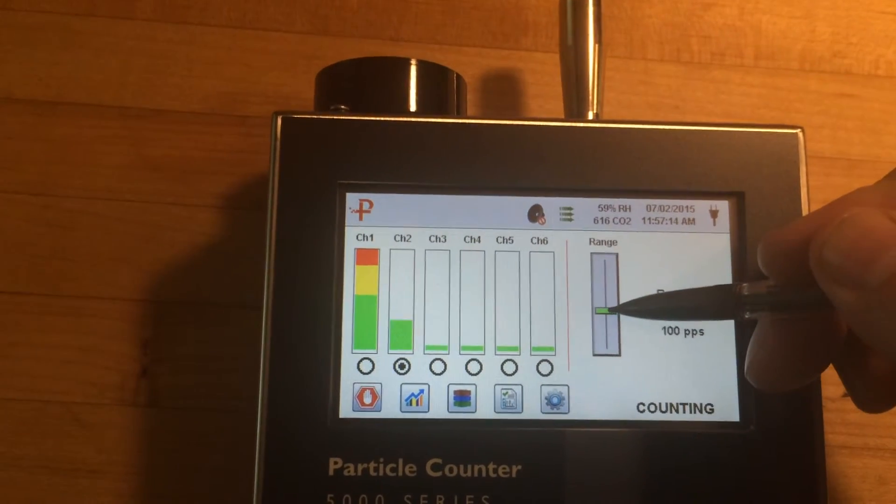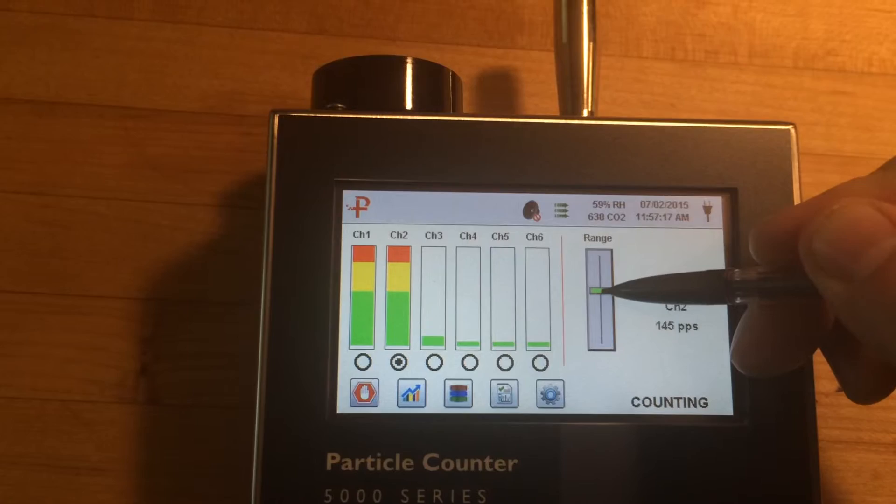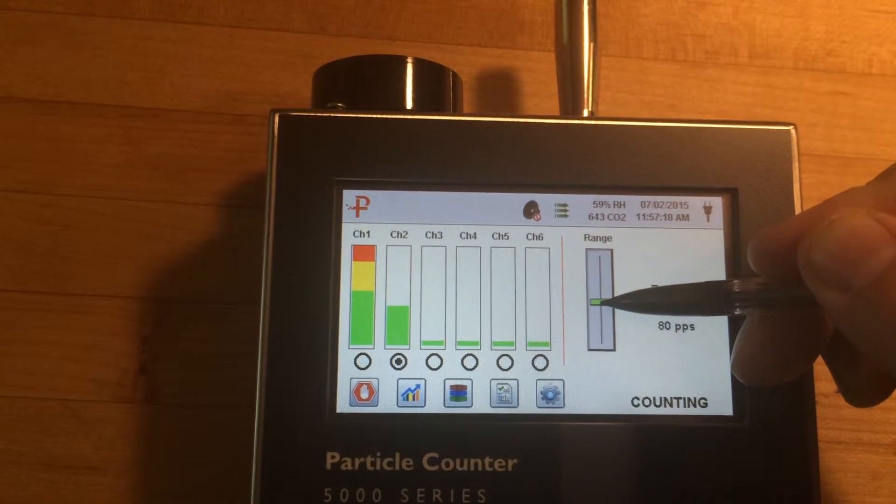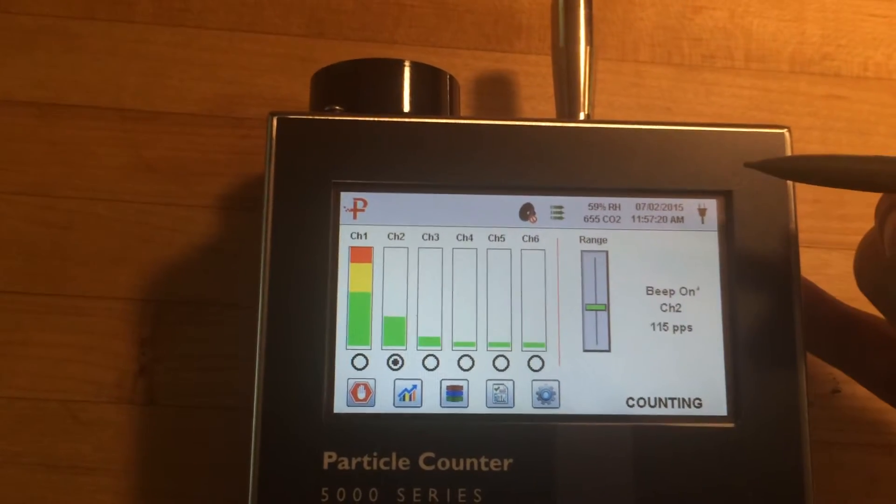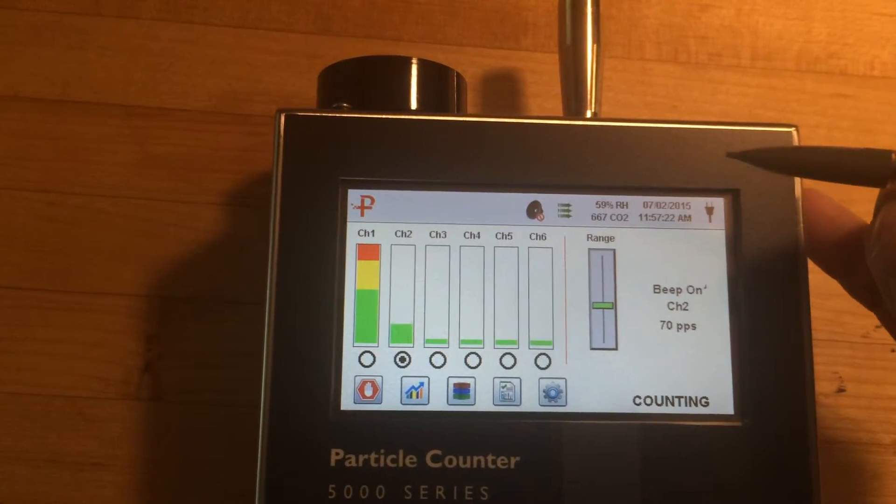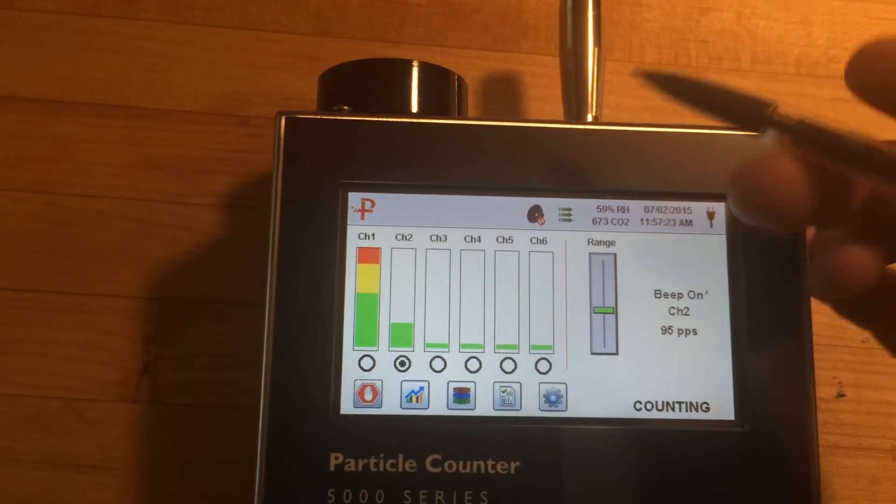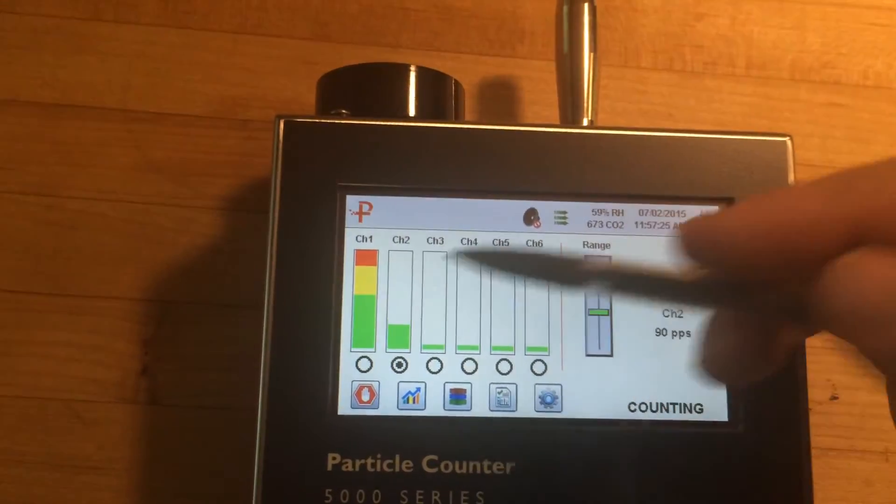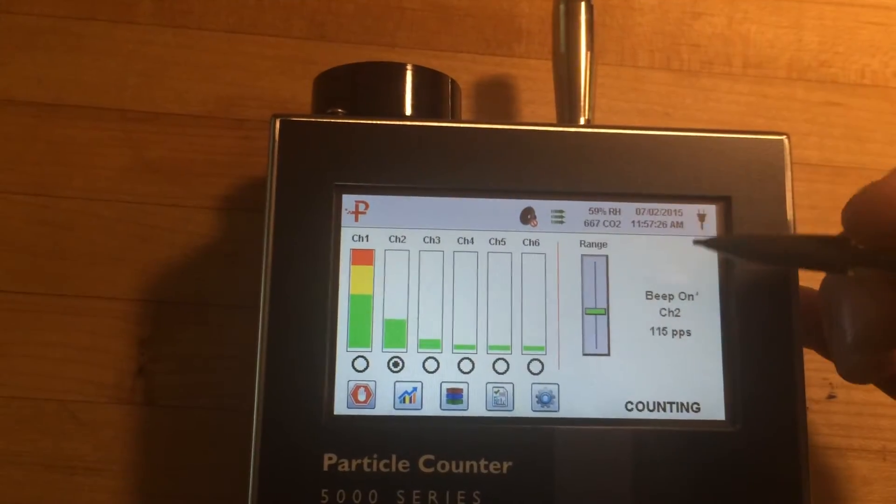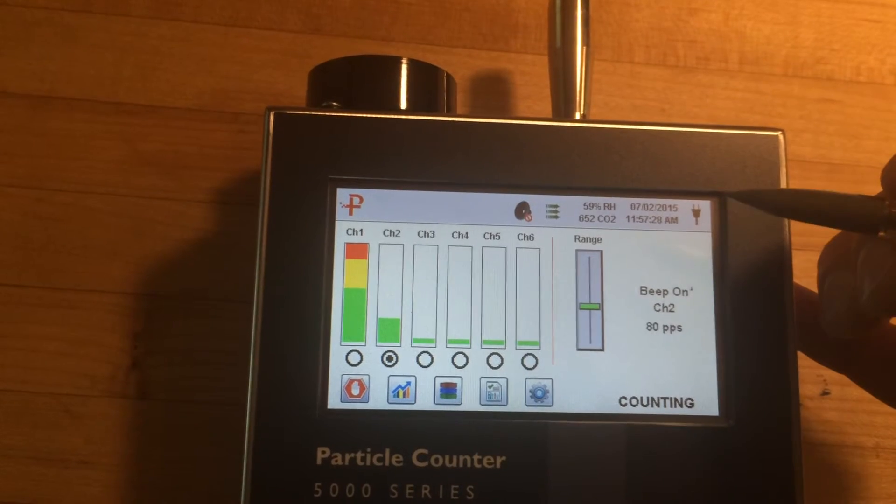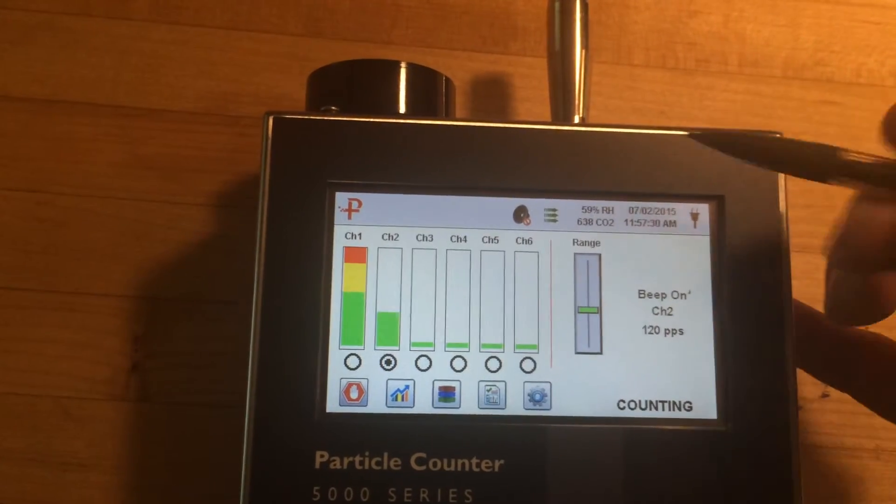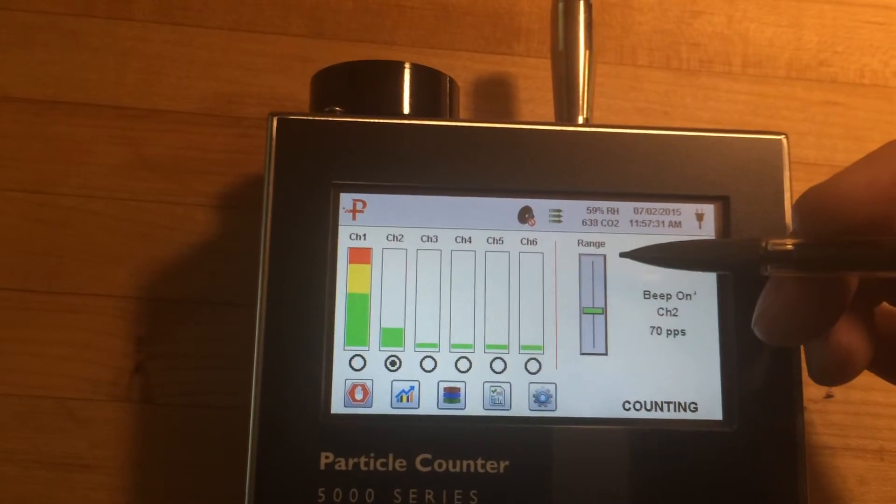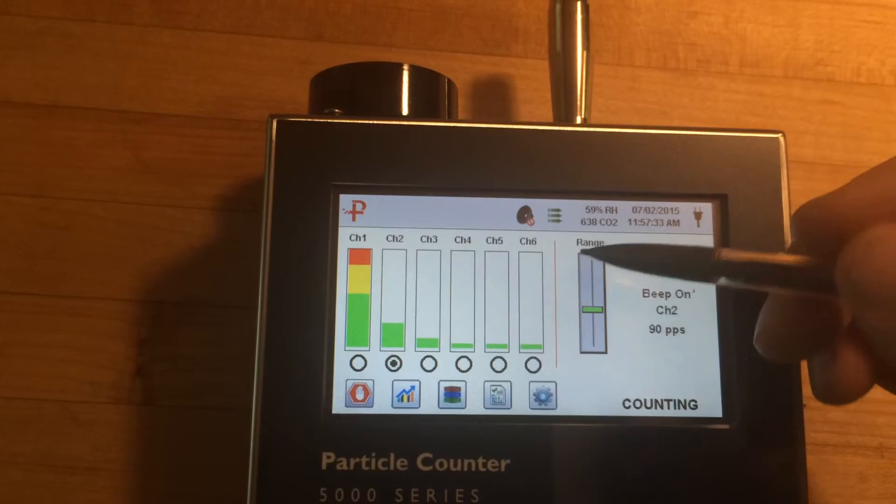This is its sensitivity meter here. So I can make it really sensitive so it spikes. But then I can back it off and then go walk around with this unit and try and figure out where the source of those particles are. So if you know you have an issue or you suspect you have an issue, you can actually use this real time to sniff out issues, which is pretty slick.